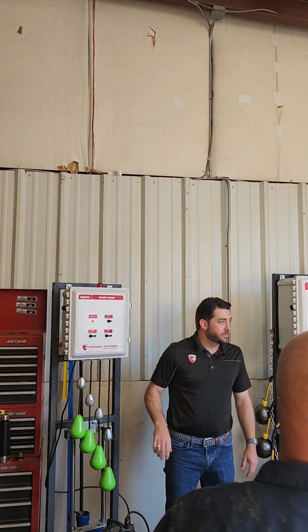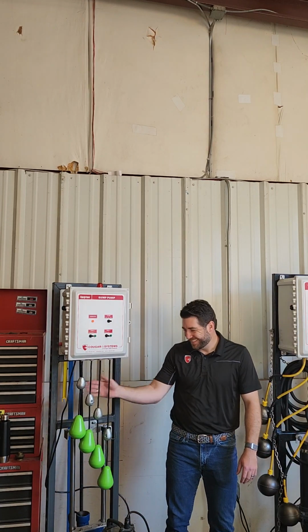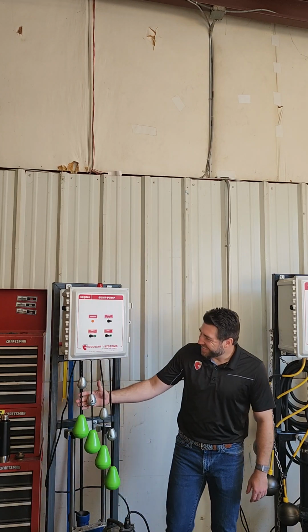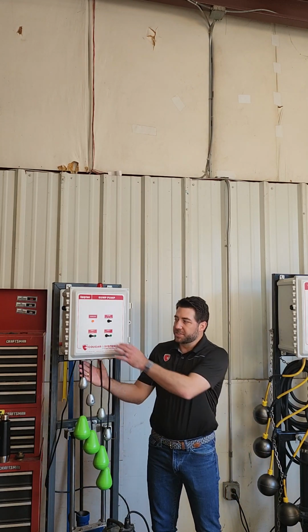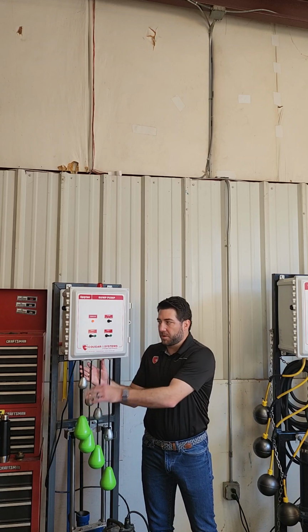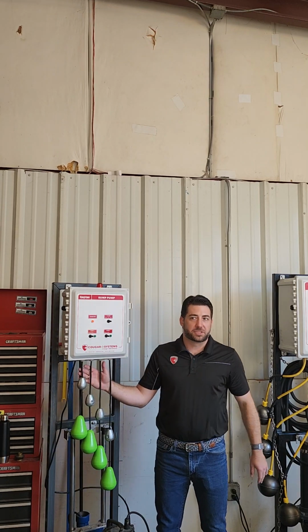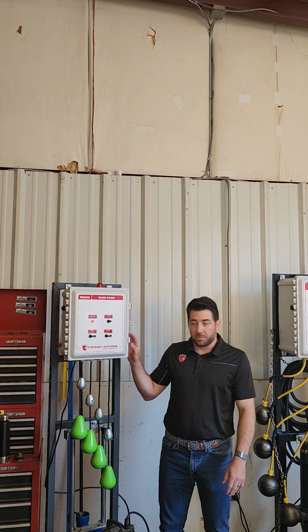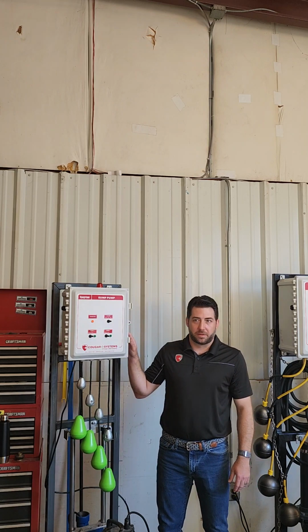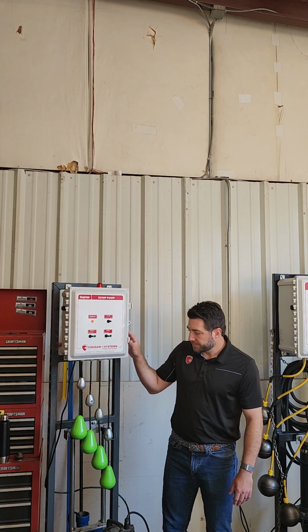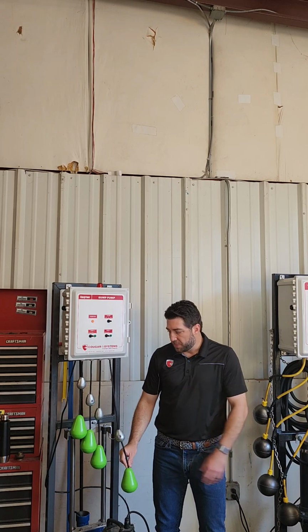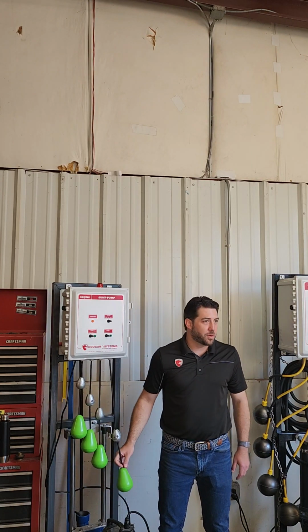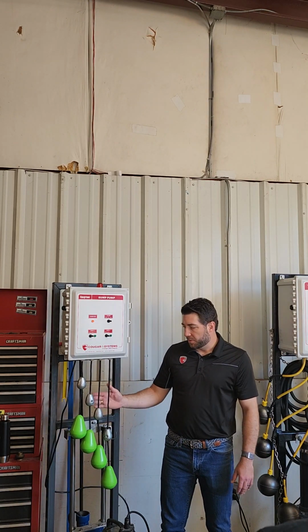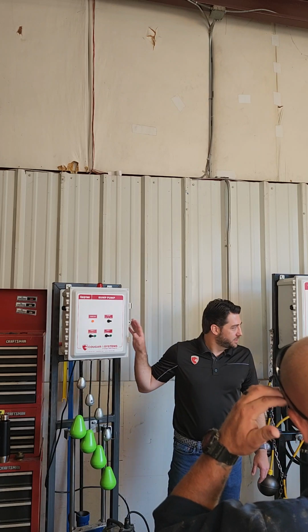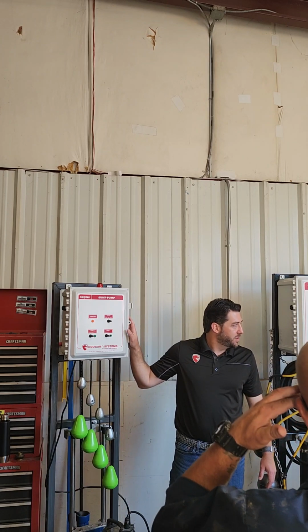Basically, it means always get Cougar. There we go. Like that. But it is just something to be aware of, that the high level alarm here typically is not going to turn on pumps. It's just going to be an alarm. So if you get an alarm with these types of panels, you really want to try to address it ASAP. Okay, so testing for this bottom float and this top float, making sure those are working, is going to be critical. Okay, so is there anything else to add on these types of panels before I move on?